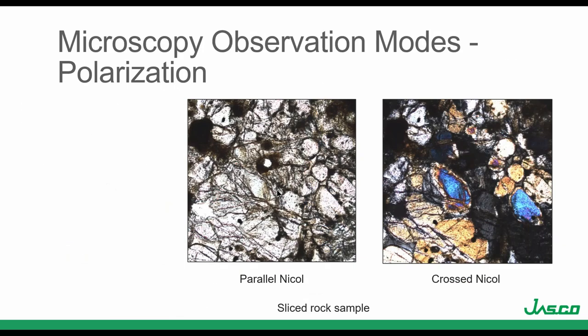Another observation mode is polarization. The light gets polarized, and if the sample can be polarized, we observe different phases. In this example, this is a thin rock sample, which is a very common application for geological samples using the polarized mode. In the image we cannot see any different phases at first, but when we apply polarization at 90 degrees, a different phase can appear, allowing measurement in those different areas.